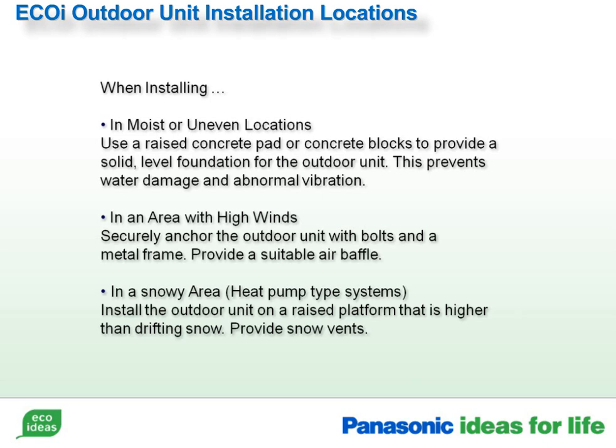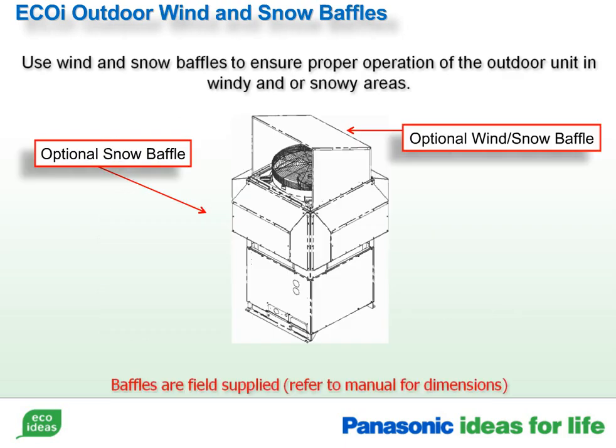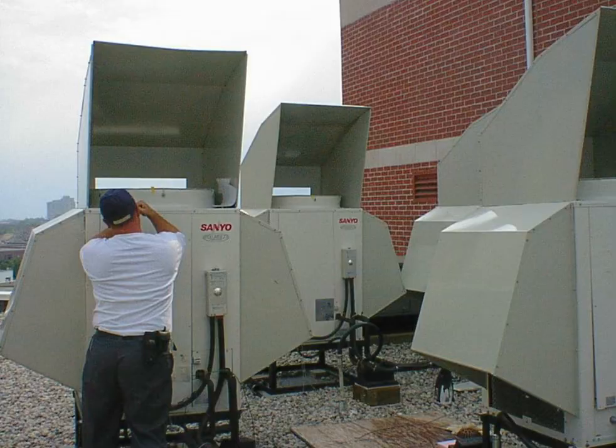To avoid this, install the unit on a raised platform and provide snow vents. In areas prone to high snow amounts, it is important to use snow shields and wind baffles. Wind baffles are available for the U-LE, but all others are field fabricated. The dimensions can be found in the installation manuals. This is a very good example of the use of snow and wind shields. Notice how the units are also elevated to allow for snow, ice buildup and defrost drainage.